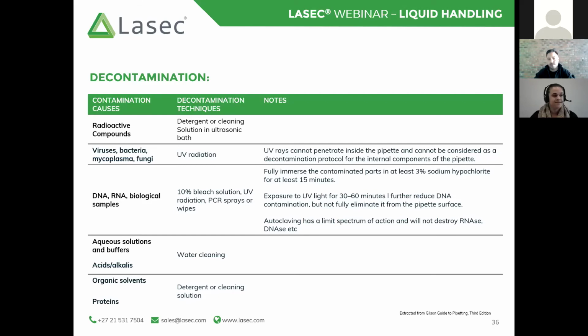However, there is a limitation in that the UV cannot penetrate the inside of the pipette. So while it is a good means of decontaminating the exterior of the pipette, perhaps once you are done working, if you've got a UV light close to the bench that can be contained, you can place your pipettes in this area and expose them to that UV light for a couple of minutes in order to decontaminate them before using them again. But this does not decontaminate the inside of the pipette, unfortunately. Okay, for those internal components, you would have to use a different method, perhaps also the bleach solution or a detergent or cleaner in an ultrasonic bath.